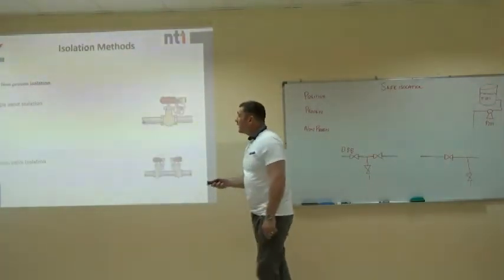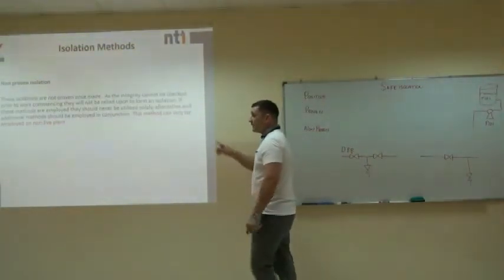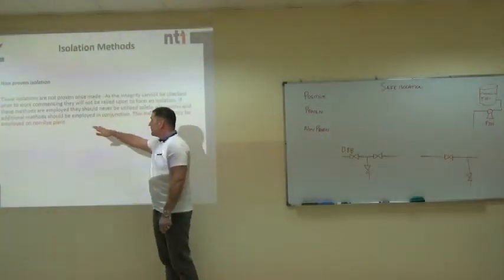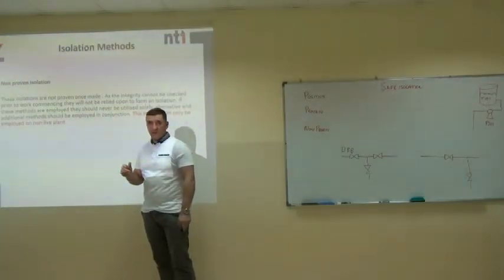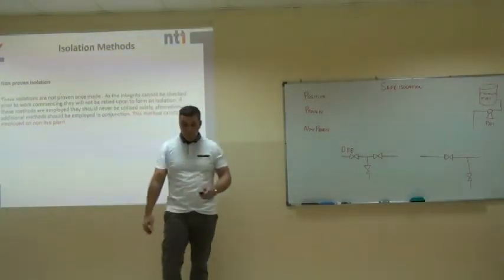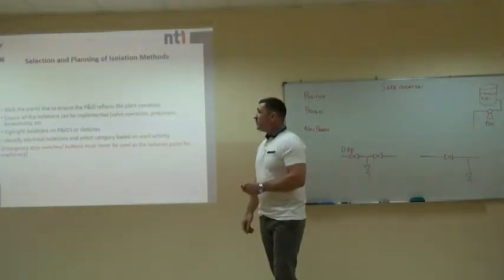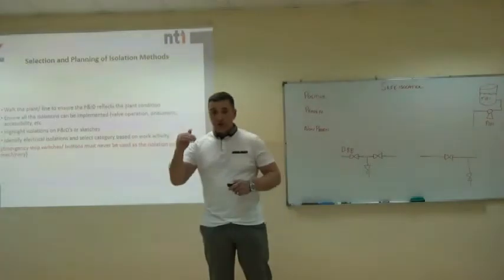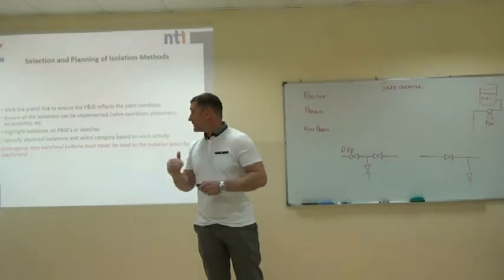Positive, proven, non-proven isolation. Non-proven isolation — the lowest form — should only be used on non-live equipment during shutdown. We should walk the line, ensure the P&ID reflects plant conditions, and make sure we use the most suitable isolation methodology for the hazardous energy we are trying to isolate.